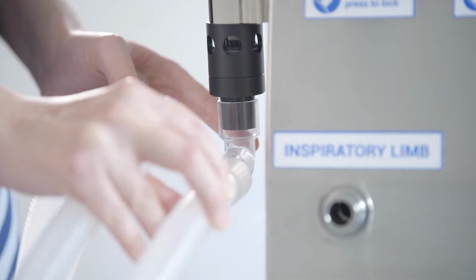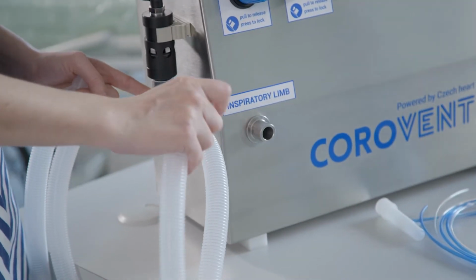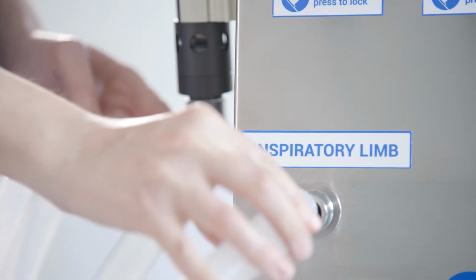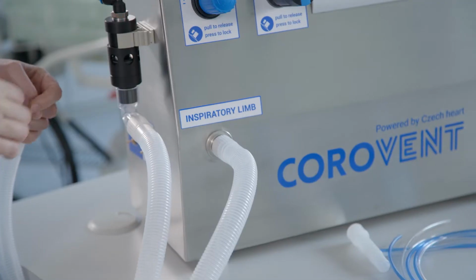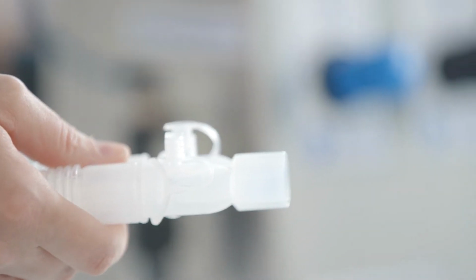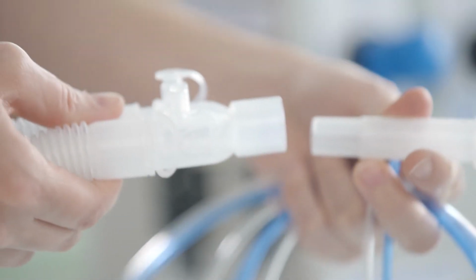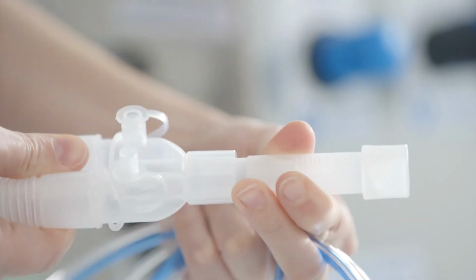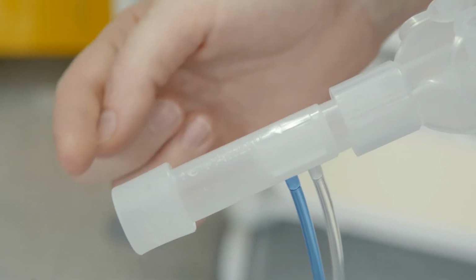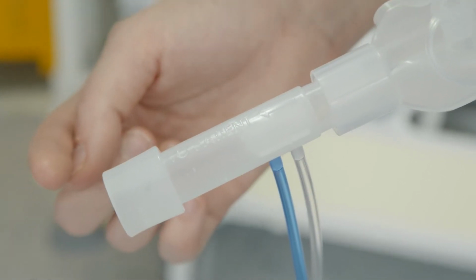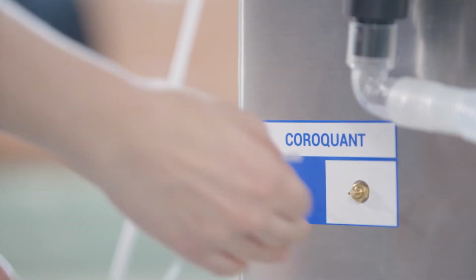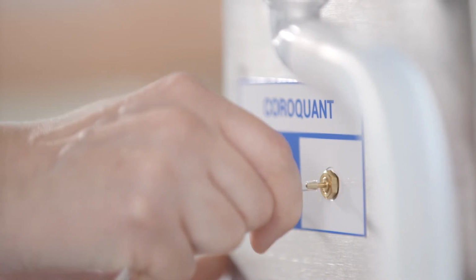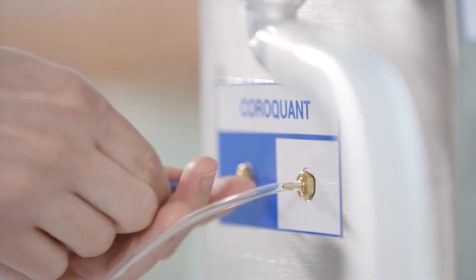Connect one limb of the breathing circuit to the lower part of the expiratory valve, the other part connect to the inspiratory limb. Then, connect the flow and pressure sensor CoroVent to the Y connector of the breathing circuit. The correct orientation of the sensor is indicated by the arrow towards the patient. The color-coded sampling lines are connected to the side of the ventilator.